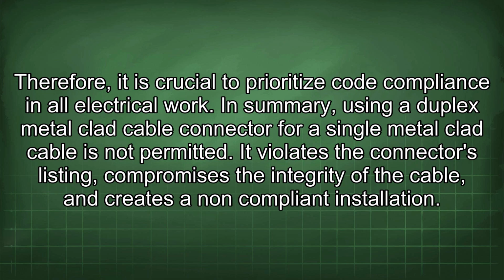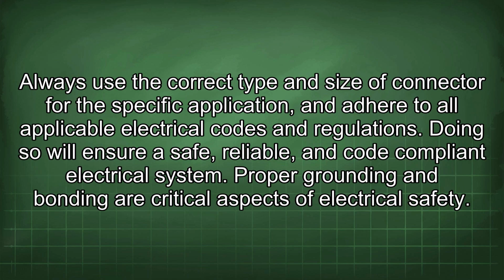In summary, using a duplex metal-clad cable connector for a single metal-clad cable is not permitted. It violates the connector's listing, compromises the integrity of the cable, and creates a non-compliant installation. Always use the correct type and size of connector for the specific application and adhere to all applicable electrical codes and regulations. Doing so will ensure a safe, reliable, and code-compliant electrical system.